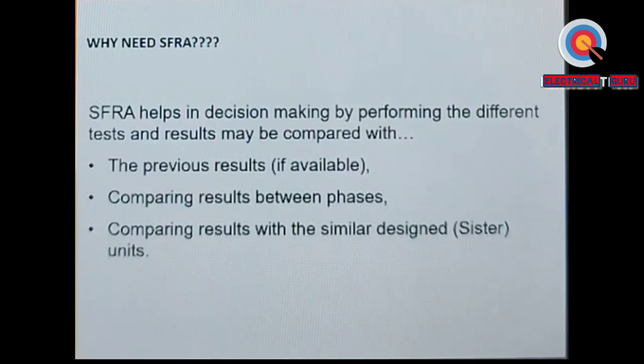So to identify the nature of problems, it is not only whether there is a problem or not, but what type of problem the transformer has suffered. We can find that out, and based on that we can decide whether it will have to go back to the manufacturer for repair or it can be repaired at site. So this type of decision is possible with the SFRA test.